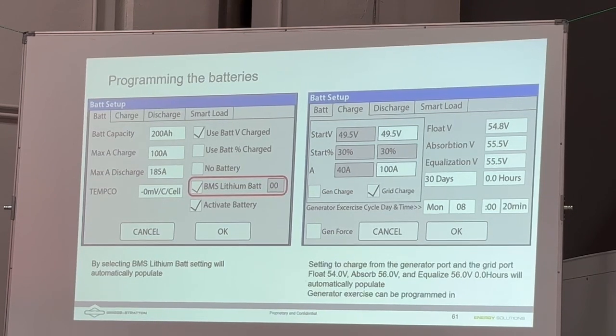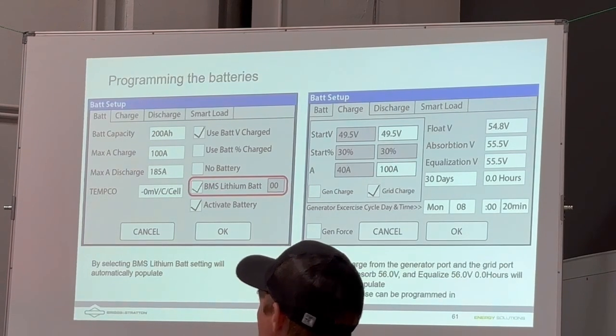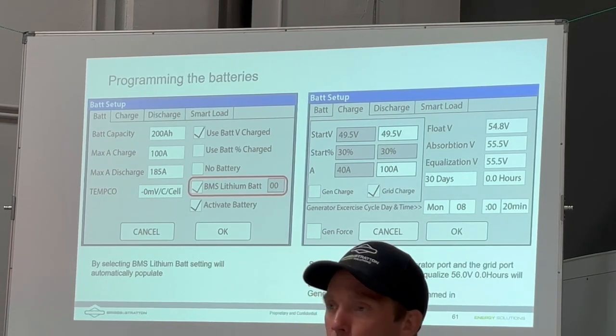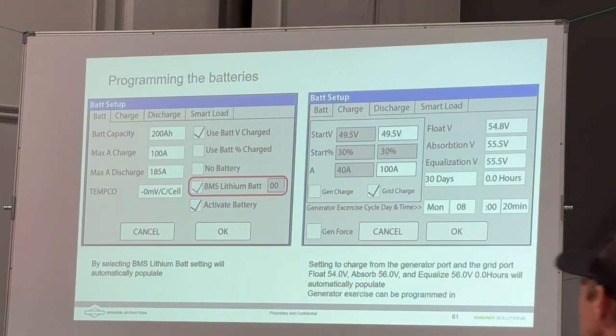So the first thing you do when you go to set up or work on setup for your system is to come into the battery setup tab and check the BMS lithium battery. That way it knows you've got a communicating battery hooked to it. As soon as you do that and click OK, the batteries will start outputting 48 volts and the system will function properly. The default is 00, that's the address for the CAN bus communications. And if you check this activate battery, it allows the inverter to turn on the battery and turn off the battery by itself.